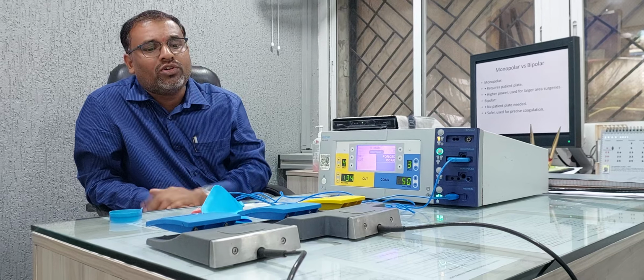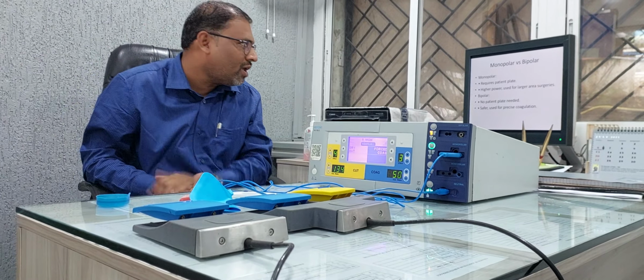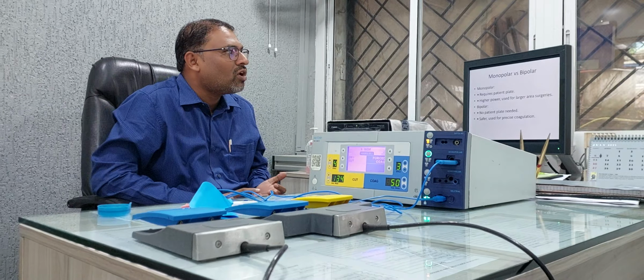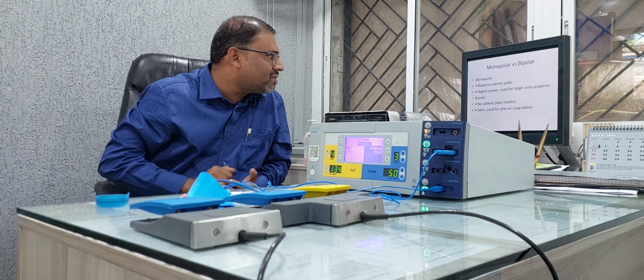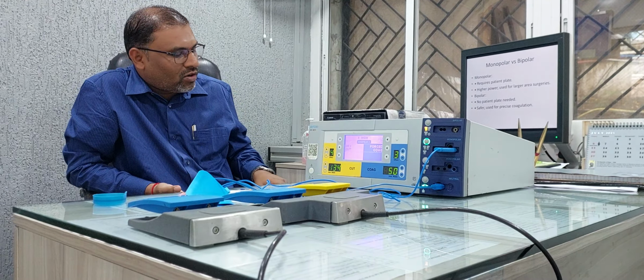So as I told you, what is the difference between monopolar and bipolar? The monopolar requires a patient plate, and high power is used for large area surgeries. The bipolar doesn't require a patient plate, right? And it is safer, used for precise coagulation. Where you require a precise coagulation, you can go for the bipolar cautery.